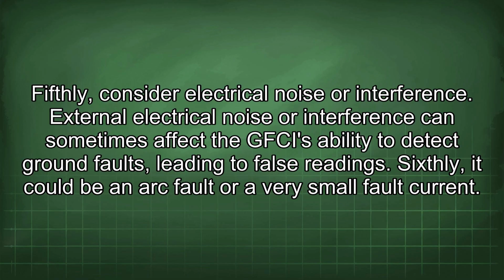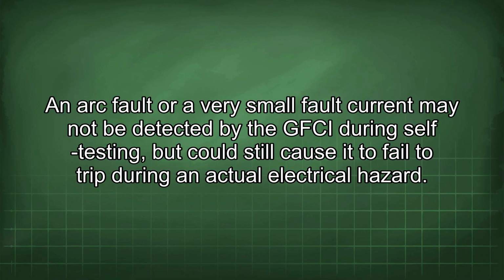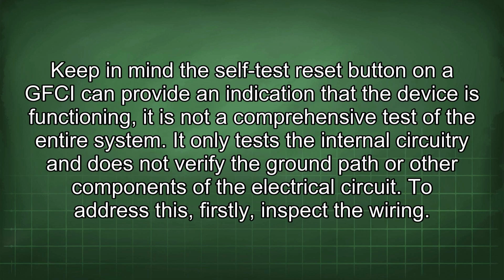Sixthly, it could be an arc fault or a very small fault current. An arc fault or a very small fault current may not be detected by the GFCI during self-testing, but could still cause it to fail to trip during an actual electrical hazard. Keep in mind the self-test reset button on a GFCI can provide an indication that the device is functioning. It is not a comprehensive test of the entire system. It only tests the internal circuitry and does not verify the ground path or other components of the electrical circuit.